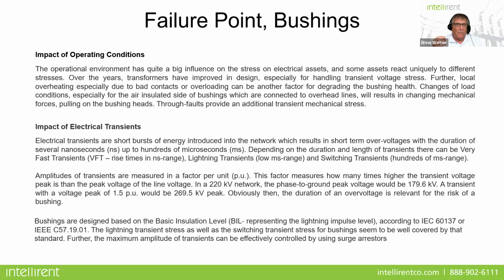If you're under a breaker failure condition, that through fault duration is going to be much longer than it normally would be. If you have a slow breaker, transients can be very, very damaging, both to your bushings and to your transformers. But we know that bushings are designed based on your BIL, or your basic impulse level, and that represents the lightning impulse level, actually.